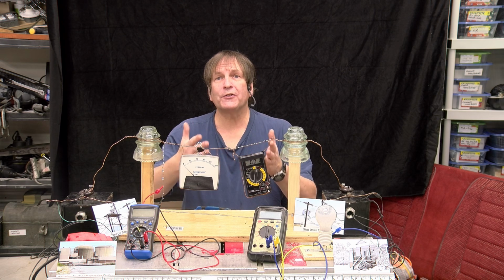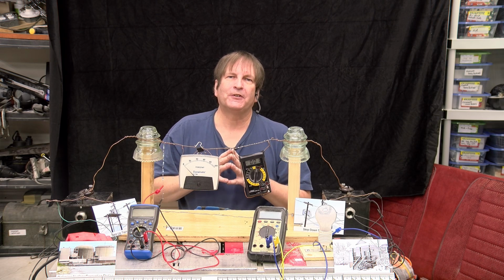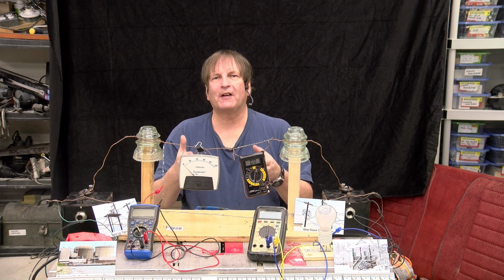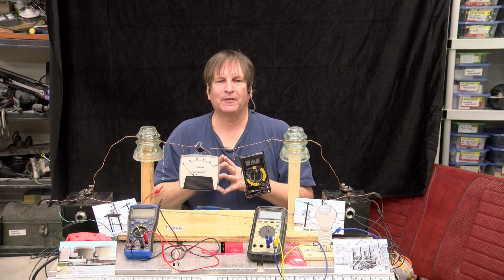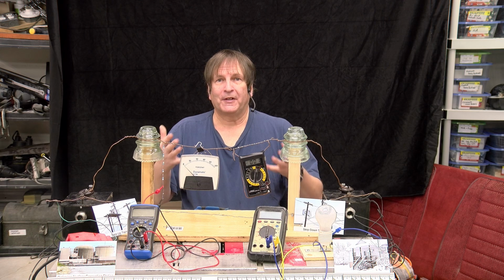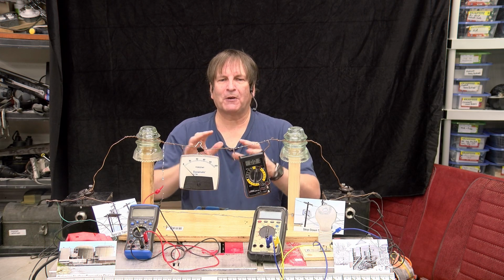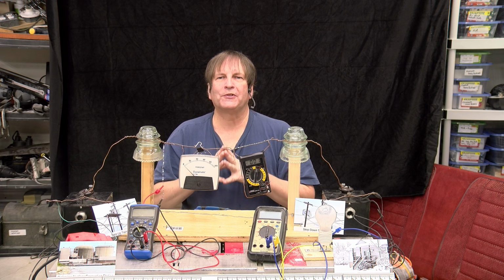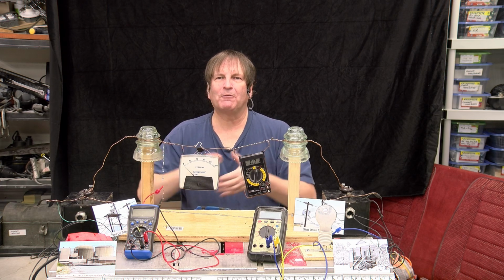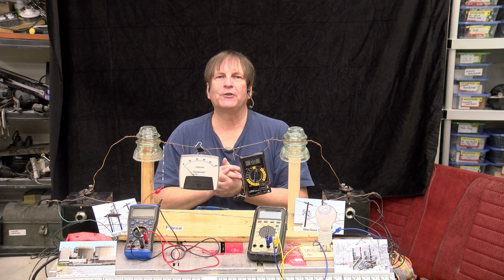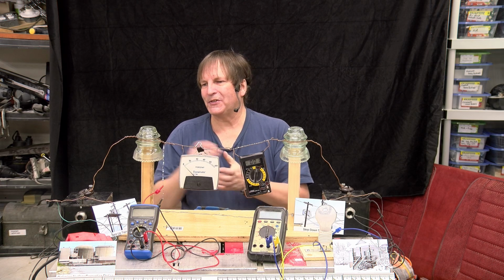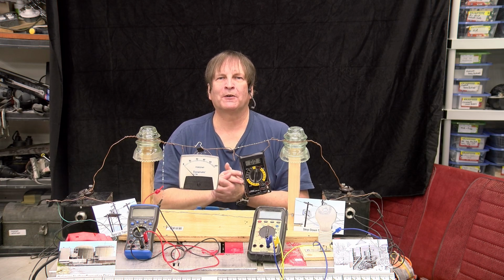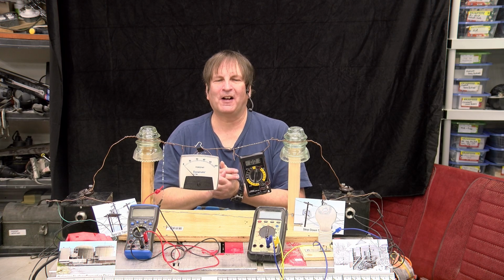So those are a couple of considerations that you have to take account besides just the resistance in the wire when you're dealing with high voltage, high current power transmission. When we are talking about the losses, in our little experiment here, I did a bit of a hand-waving discussion as to what the losses amount to and how, by stepping up the voltage, we can essentially reduce the losses by the step-up amount squared. So if we step up the voltage by 10 times, we can reduce the losses by a factor of 100.